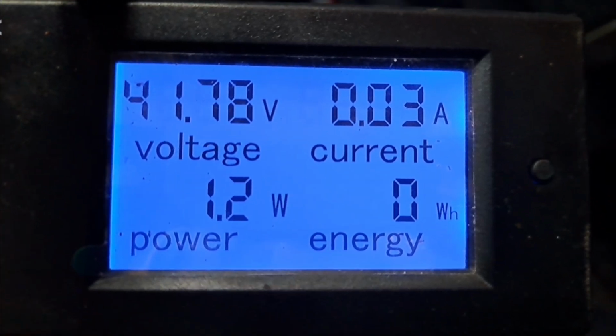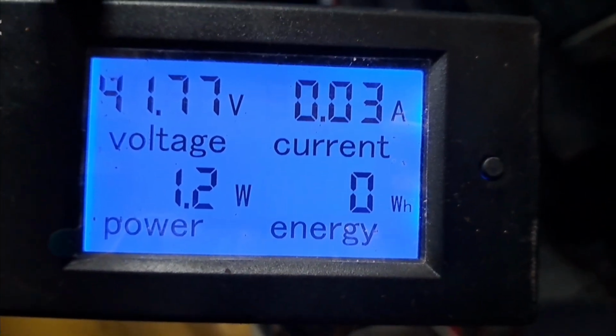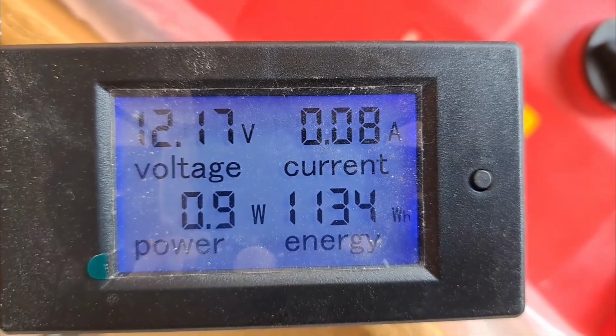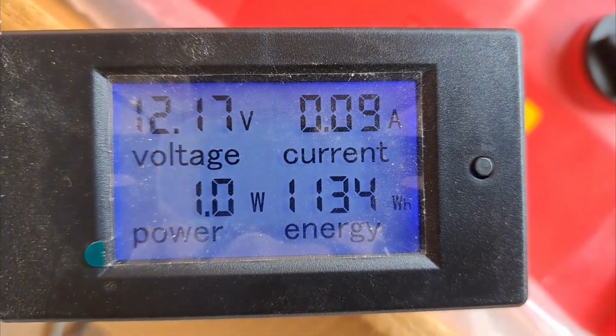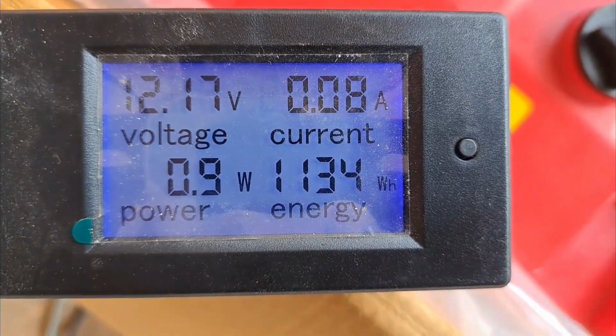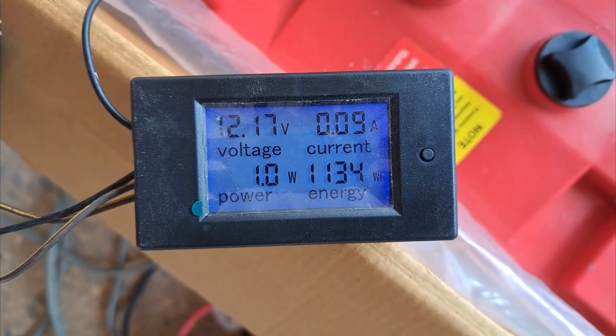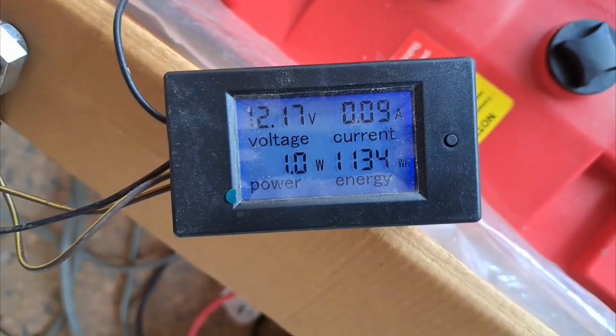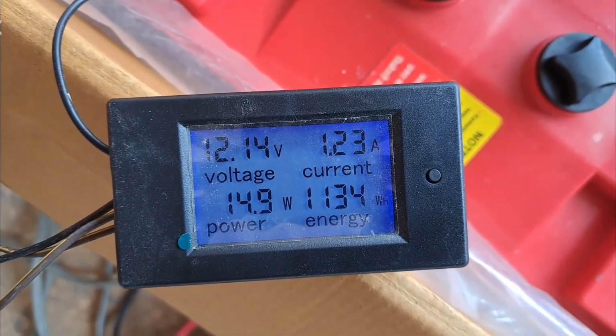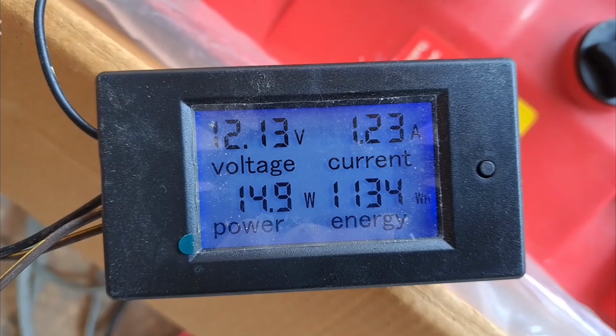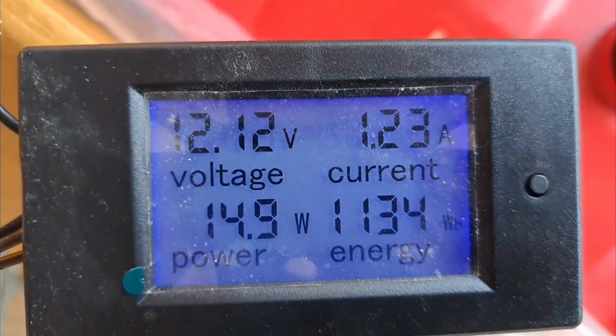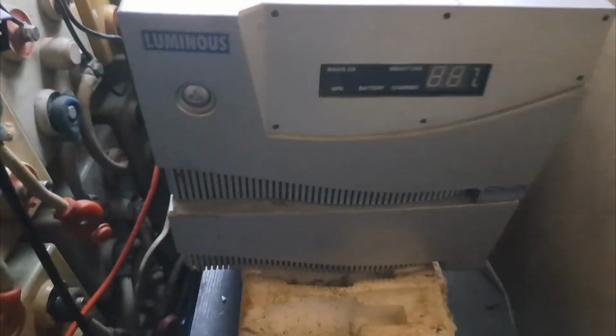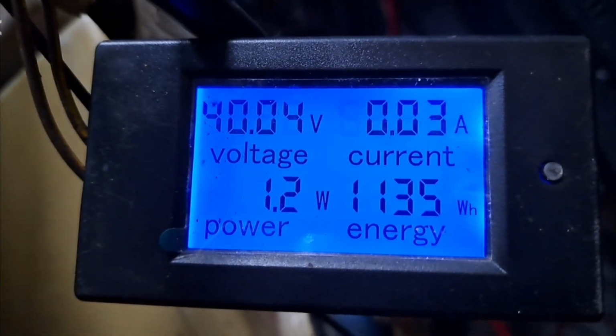Let's do the math for lead acid batteries. They're expected to give you half the capacity of the battery rating. So if you have a 200 amp hour battery, at the end of the day it's going to give you around 1200 watt hours. If you connect this 2.5 kVA inverter to that battery, in just one day it's going to run the battery down without even connecting any load to it.